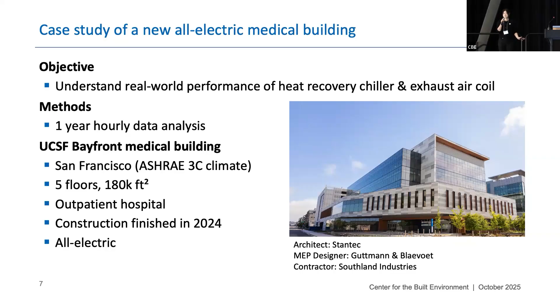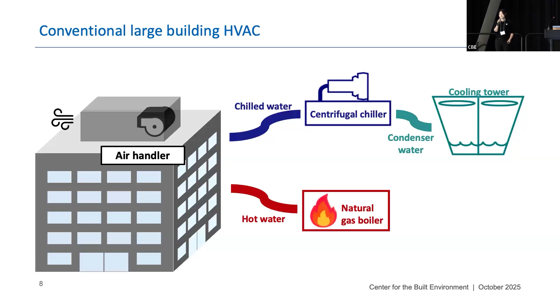Conventional large buildings often use chillers paired with cooling towers for cooling and natural gas-fired boilers for heating. As you all know, natural gas-fired boilers create large carbon emissions, and cooling towers consume a large amount of water. Heat recovery chillers can address this challenge by capturing the waste heat from cooling and reusing this waste heat for heating. But in practice, buildings' cooling demand and heating demand are not perfectly matched in real time. So, since the heat recovery chillers run to meet the higher demand, there is excess energy on the lower demand side. To manage this imbalance, our case study building uses exhaust air coils.